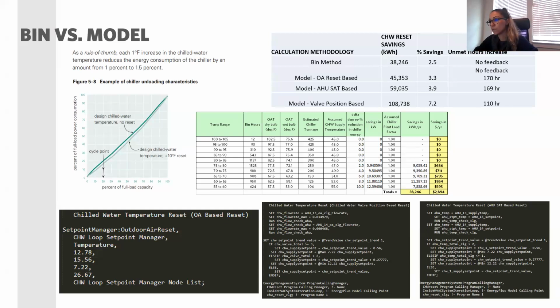And the last one, which I think is the most interesting, is the valve position. This is basically looking into every chill water valve and calculating if the valve is more than 90% open, then we start flagging. And if more than this many valves are open, let's start reducing or increasing the temperature. While the outside air reset was showing 3% savings, this actually showed 7.2%, while also having fewer unmet hours. So this is where I guess we can say the energy model becomes more important if you want to get into this level of analysis for a project.